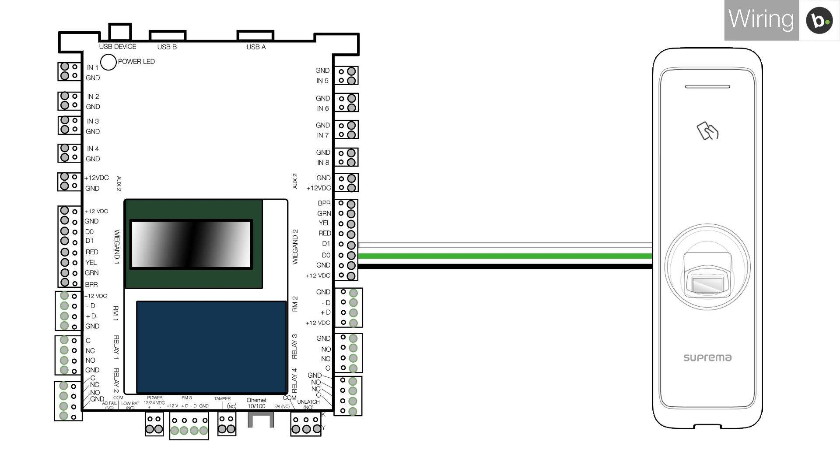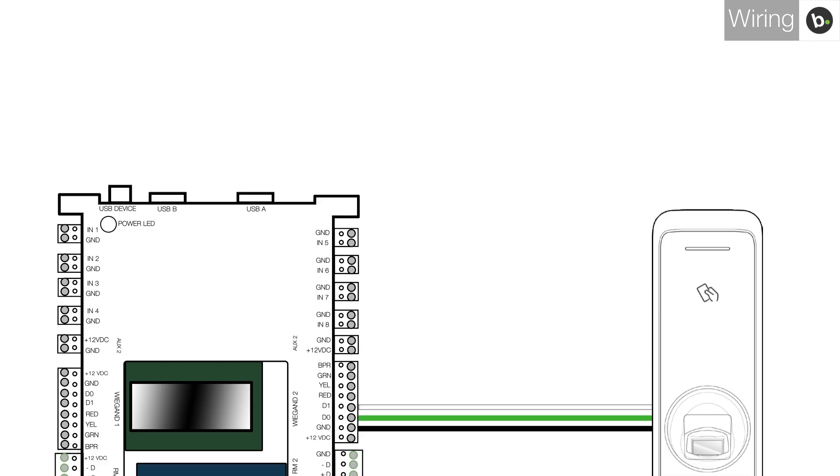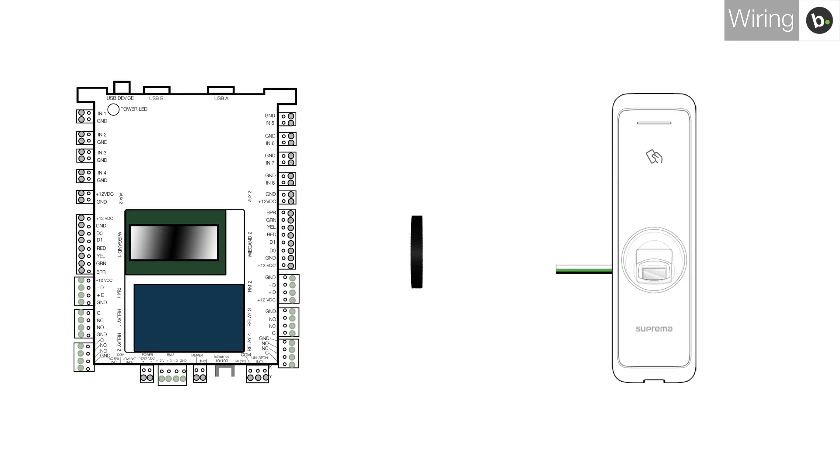Finally, you'll want to try wrapping your wires around a ferrite core. A ferrite core was included in your reader's box. Wrap the wires around the core twice and reconnect them to the panel. This will eliminate any electromagnetic interference that may be blocking a signal.